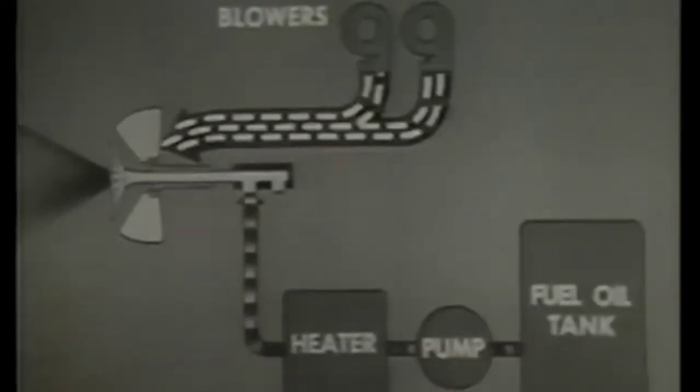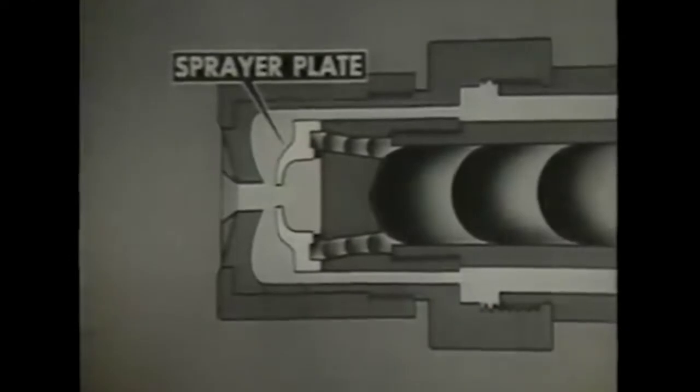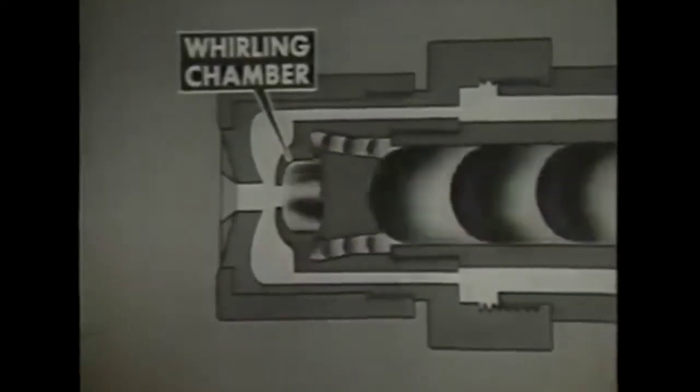In this type of burner, only part of the oil that goes through the burner is actually burned. The remainder returns to the fuel oil pump. Air doors and a bladed cone give the whirling motion to the air that enters the register to mix with the oil, as in the burner seen previously. The oil, heated and under pressure, is forced through the inner tube of the burner to the sprayer plate, where the oil is rotated in the whirling chamber. The oil leaves through the sprayer plate orifice. Centrifugal force sends some of the oil into the return line and back to the fuel oil pump. The remaining oil continues through the orifice into the furnace.